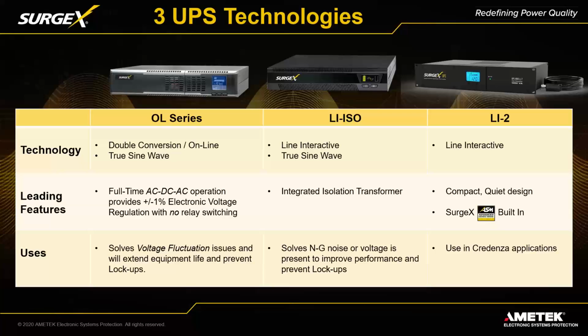We were able to plug in the line interactive unit with the integrated isolation transformer and drop that neutral to ground voltage down to well below 1 volt—I think we were at 0.125 or 0.233.